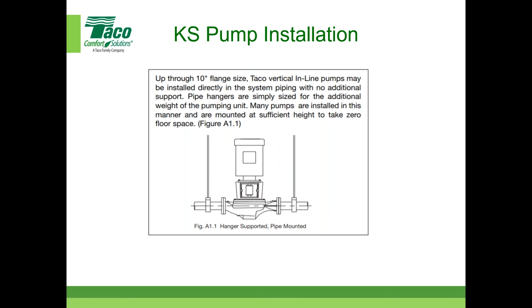Here's something we've seen before for smaller pumps - typically 15 horsepower and below, they can be mounted even closer to the ceiling. You can see some of the hangers above the finished floor, even closer to the ceiling. Then you put the multi-purpose valve at a right angle on one side to help the pipe go straight up, as well as the suction diffuser on the other side. It's a rear pullout, meaning the screen pulls out to this side, so you need some clearance over there as well. Here is a possibility of a different way, up to and including 15 horsepower.